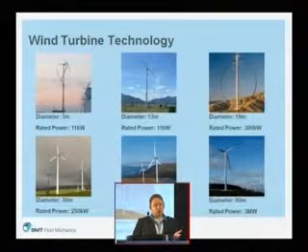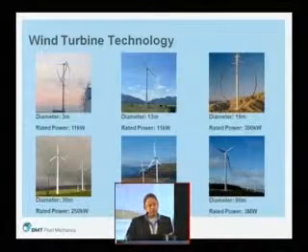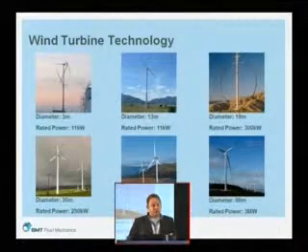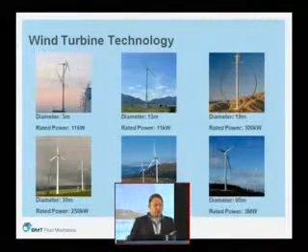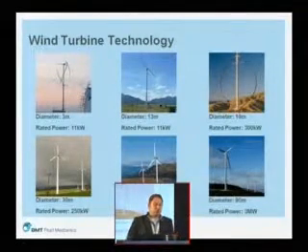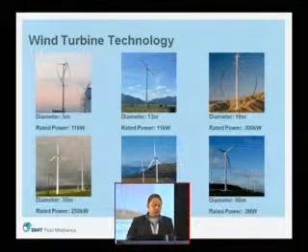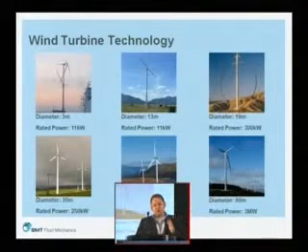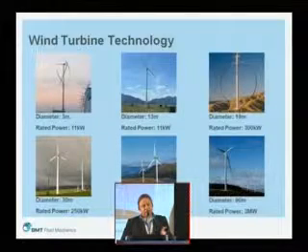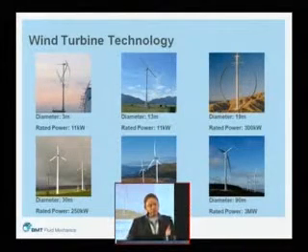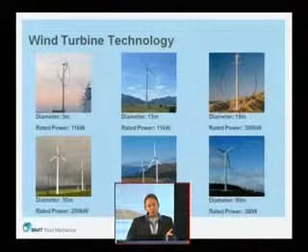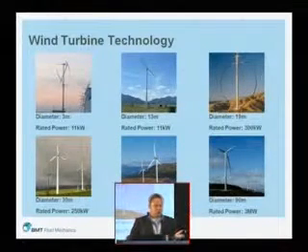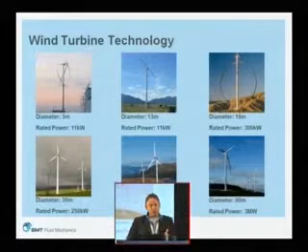In Bahrain, they installed three 30-meter diameter turbines, which ultimately gave them a rated power of about 1 megawatt, which amounted to something like 12% of the energy needs of that building. So if you have a design intent of extracting something of the order of 10% of energy from the wind and supplying it to your building or to the grid, you're talking about large-scale devices.